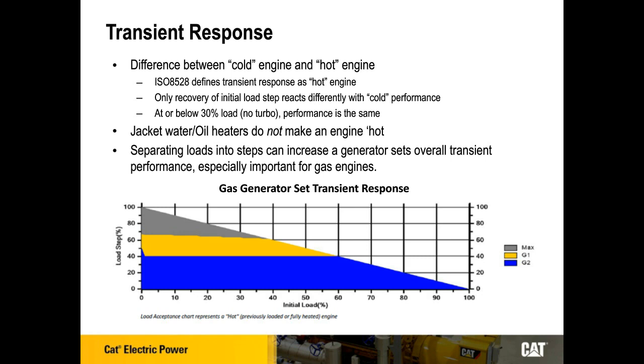To take an example, if the engine was running at 20% and then you took a 60% load step, you'd come across the x-axis to 20 and then up the y-axis to 60, and you'll see you're in the yellow range. So that means the engine was running at 20%, you added 60, so now it's at 80% load, and that would give a G1 class response, which would be acceptable for a lot of applications in terms of voltage and frequency dip.